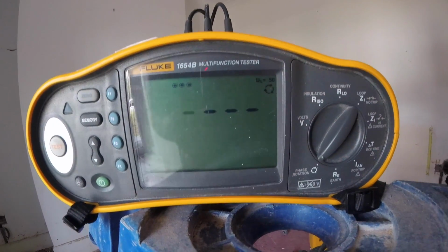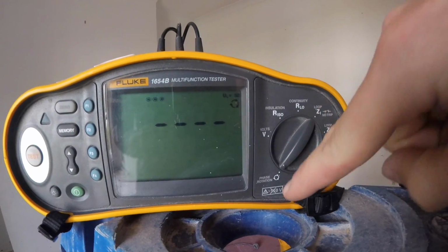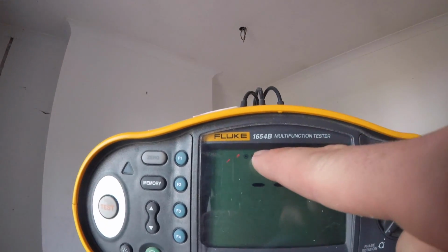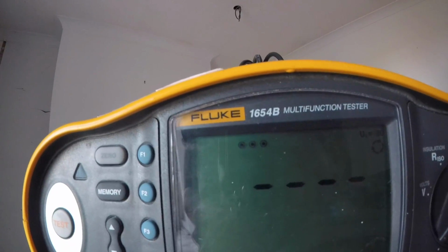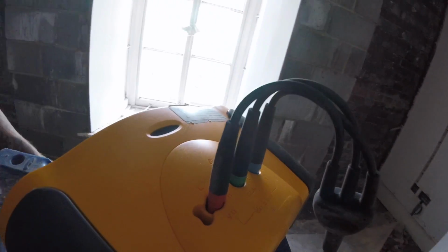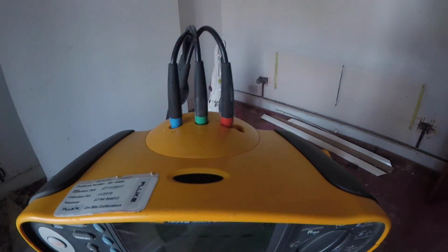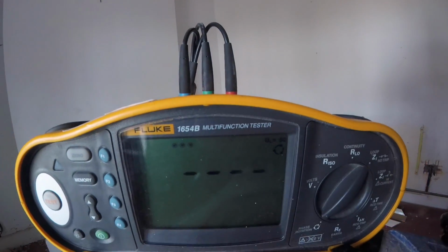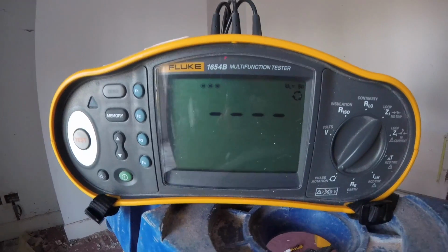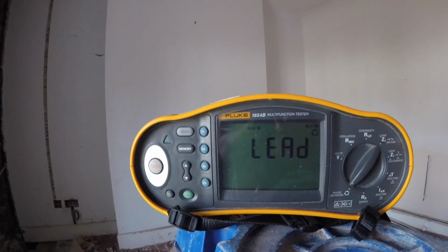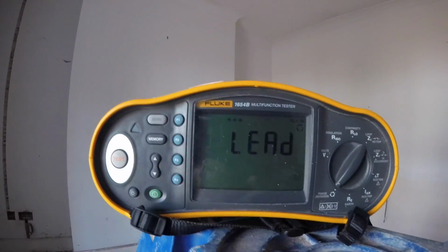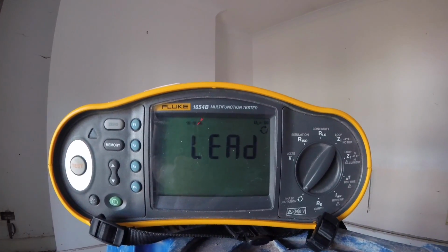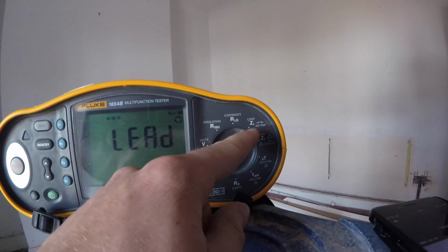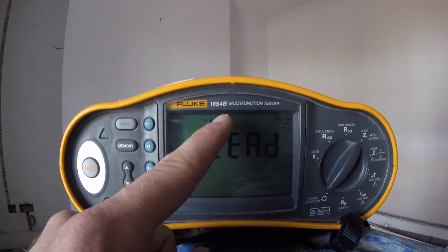And last but not least, and quite important, is your phase rotation test. So literally all you do is flick it onto phase rotation, and then up here you have all 3 leads, dots up there. And as I mentioned earlier, on each of these terminals you also have L1, L2 and L3 marked to them. So if you put all 3 of them probes onto the desired terminals, it should tell you along here whether they are all in the correct sequence. So yeah, that is basically all the tests of this meter. So another little thing to add, this also can do polarity. So say for example you're testing the earth loop, it will let you know which leads are on which terminal.